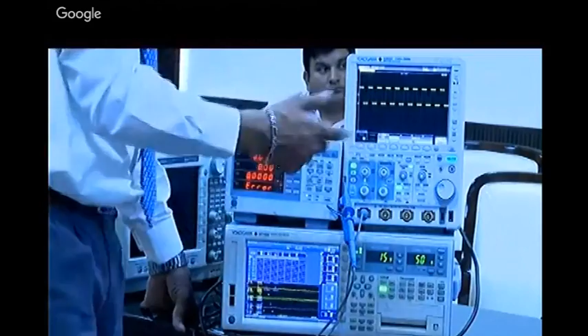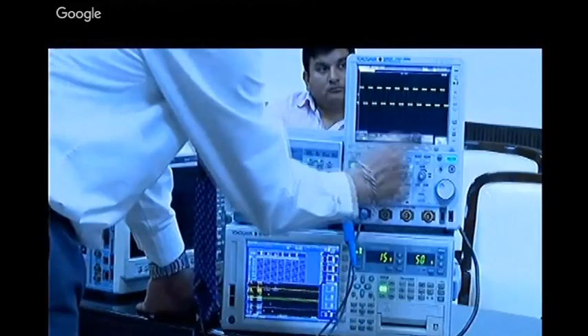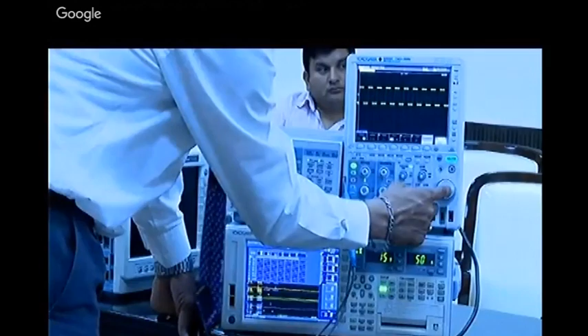This is the normal function, then there are channel functions, like display, coupling, and probe settings. You can connect a voltage probe and a current probe, and set up attenuation for a current probe at 1:1, 10:1, or 0.1:1, which you can change. You can also invert a signal, there's a linear scale which was explained, and you can label or name the channel as you want. There's also a bandwidth filter explained earlier, where you can go down to 8 kilohertz to eliminate noise and see the signal clearly, reducing from 100 megahertz down to as low as 8 kilohertz.